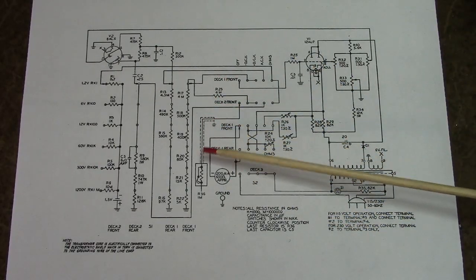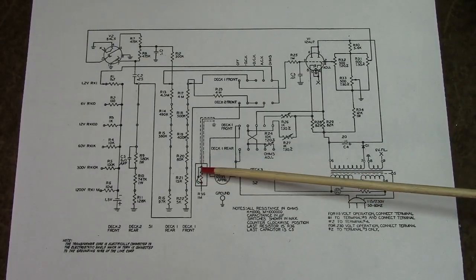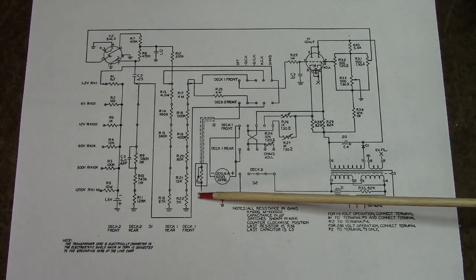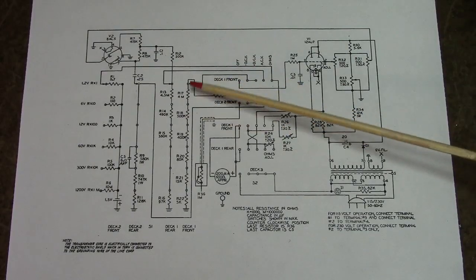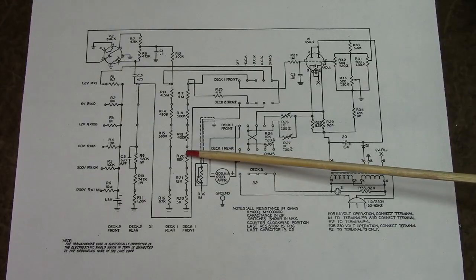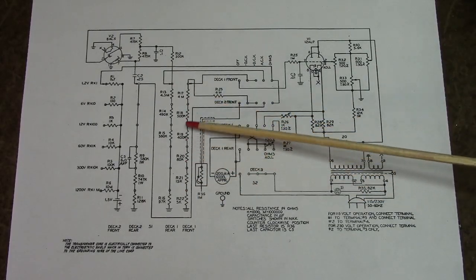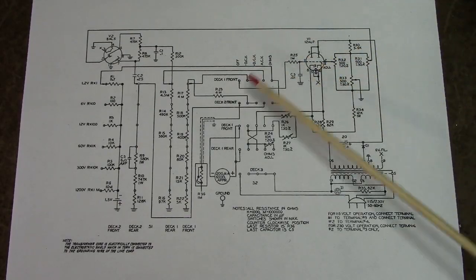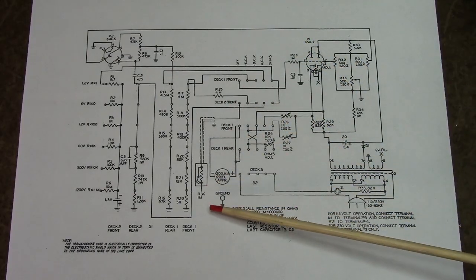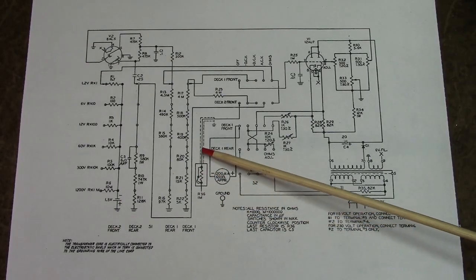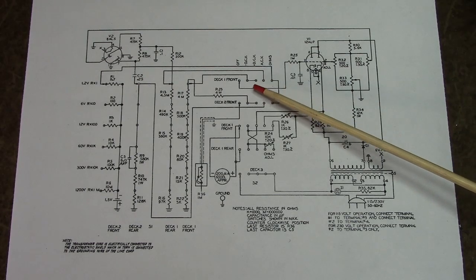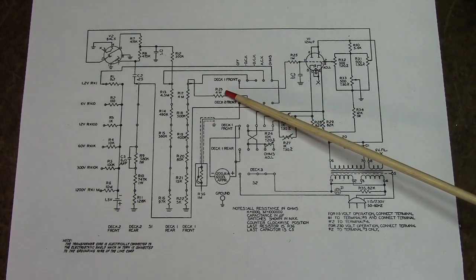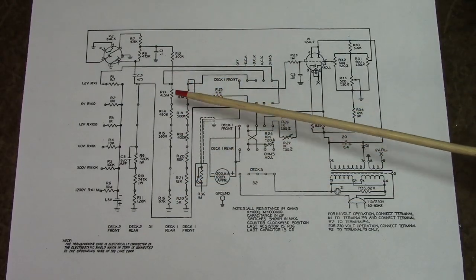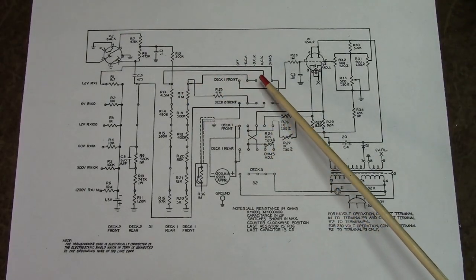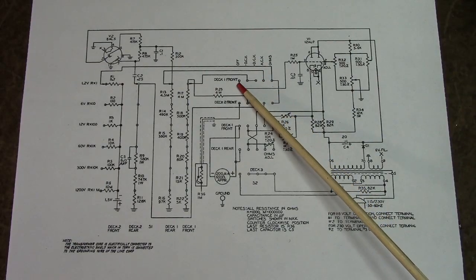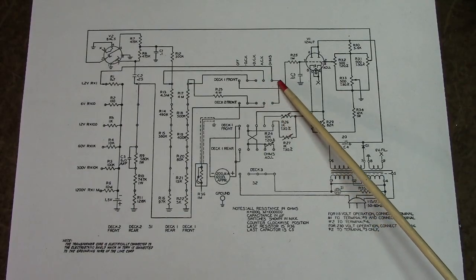If you look here, these typically had a 1 meg resistor when you're measuring DC voltages, a 1 meg resistor in series with a probe. Looking here, this string of resistors, 17, 18, 19, 20, 21, and 22, are the multipliers for the DC ranges. When you're measuring DC voltage on the selector switch on the front, for instance a negative voltage, the voltage would come up through the probe, and then through this connector switch, it would connect the probe through R23 to the top of this multiplier chain. And then the other side would be connected here. In other words, you see the arrow, this would be connected to negative or plus DC. That would connect it to the grid of the tube.